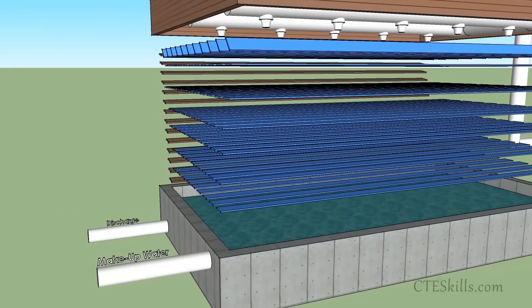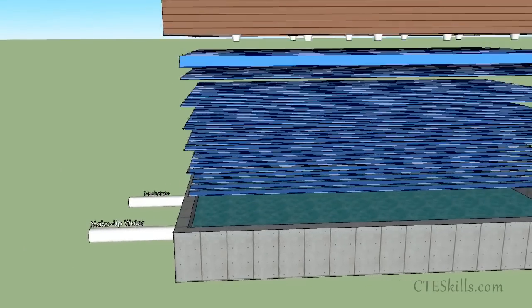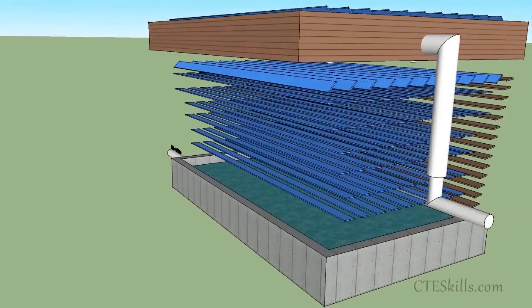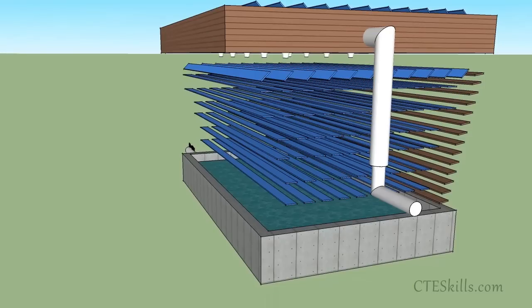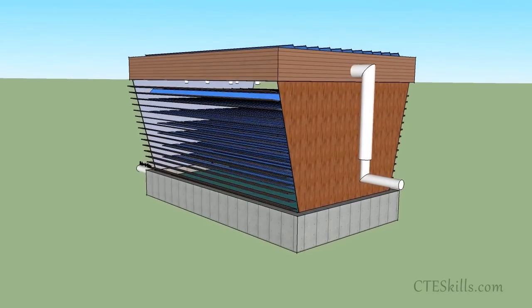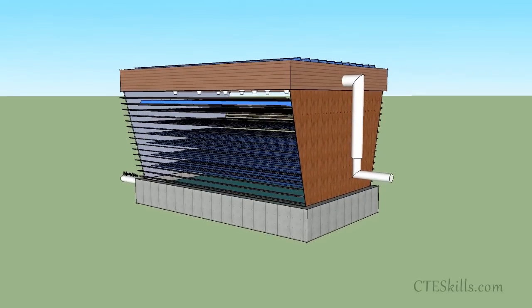Within a cooling tower you will see the use of plastic or wooden slats. These are called fill and are used to direct the flow. The purpose of this is to increase the area of contact between the hot water and the cooler air.